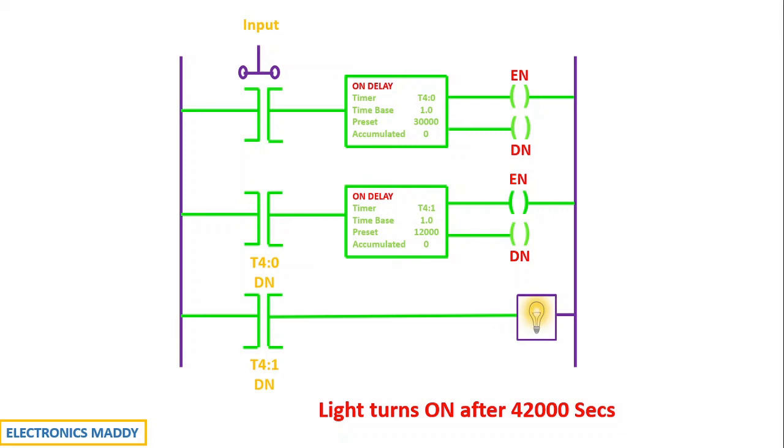if we want to count values more than 32,767 seconds, then we have to go for an additional timer. And that can be achieved by using cascading. And that is why we need the concept of cascading and it is popularly used in a lot of different applications.